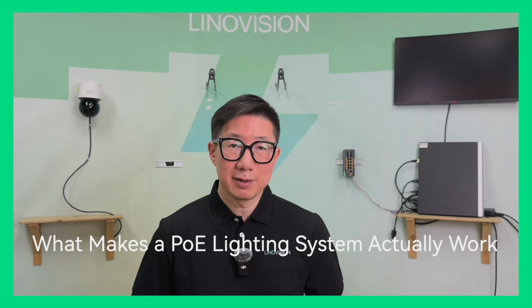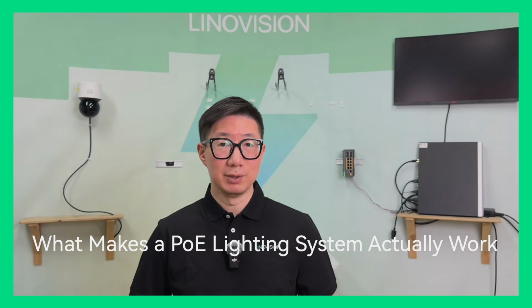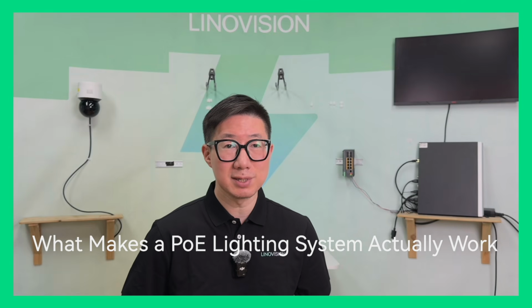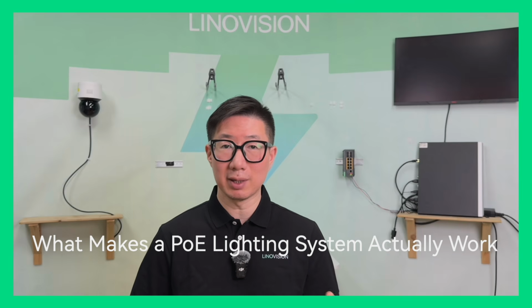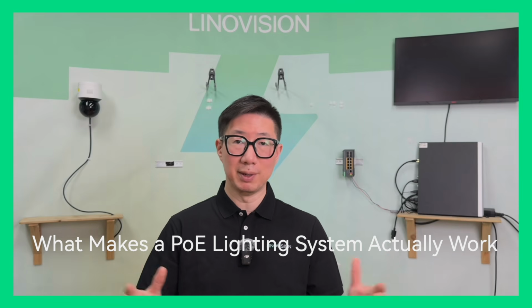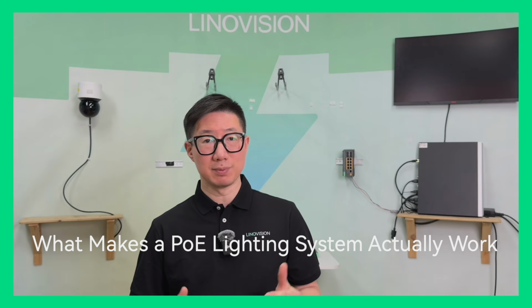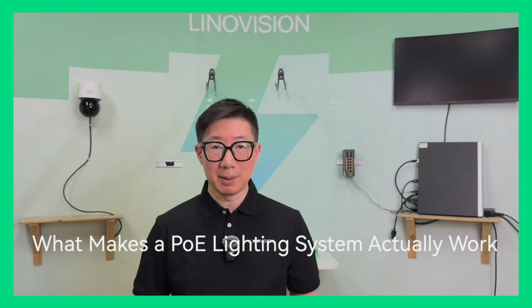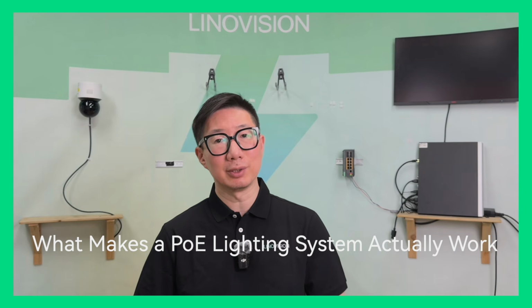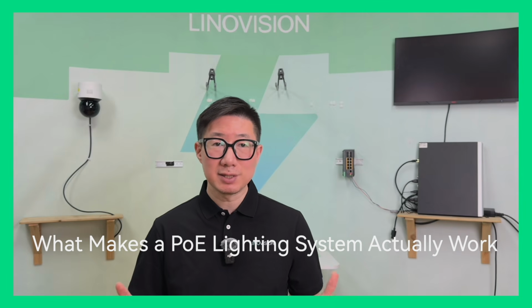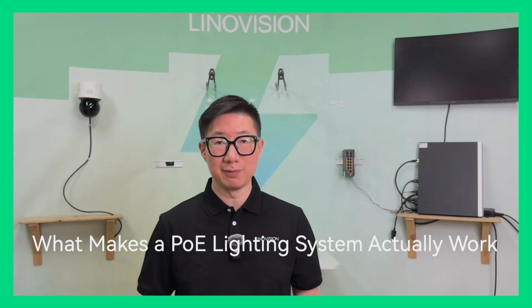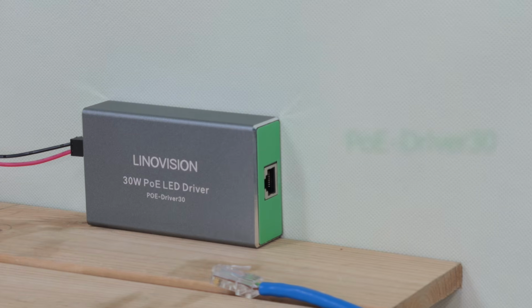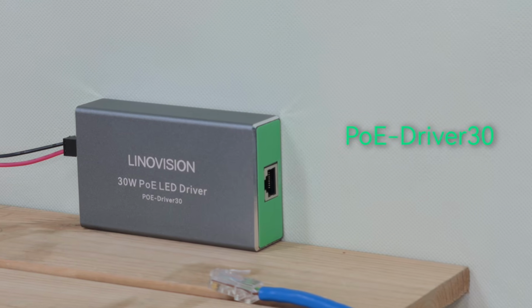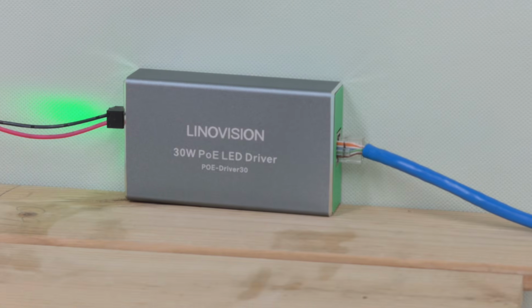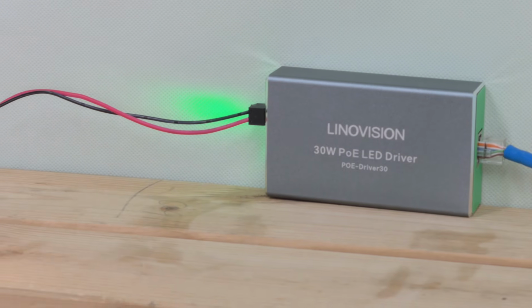If that fixture-side conversion isn't done properly, you end up with visible inconsistency between fixtures, degraded output over time, or both. And no amount of smart network management fixes the problem that's happening at the LED junction. That's why, in this design, we started with a driver, not a switch. The driver we're using at the fixture side is the Linovision PoE Driver 30, the 30 watt PoE input LED driver designed for professional lighting applications.